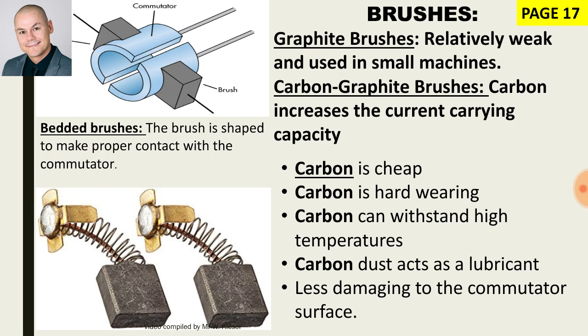We get different types of brushes — carbon brushes and graphite brushes. The term 'bedded' means that we shape a new brush to the surface of the commutator. We like carbon because it is cheap, hard-wearing, can withstand high temperature, and carbon dust acts as a lubricant.